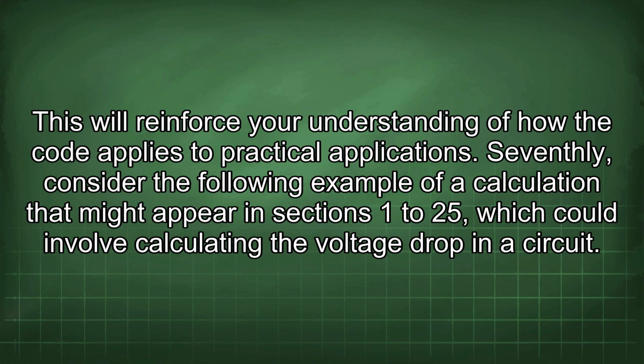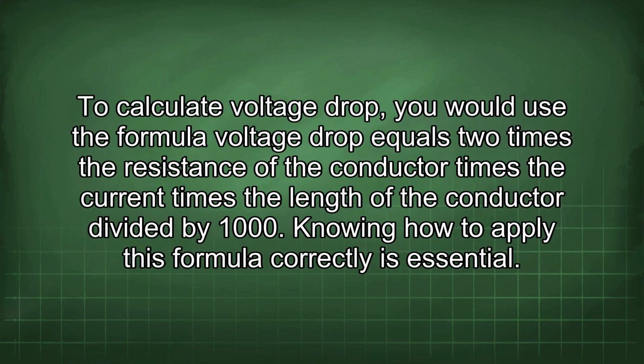Seventhly, consider the following example of a calculation that might appear in sections 1 to 25, which could involve calculating the voltage drop in a circuit. To calculate voltage drop, you would use the formula: voltage drop equals 2 times the resistance of the conductor times the current times the length of the conductor, divided by 1000. Knowing how to apply this formula correctly is essential.